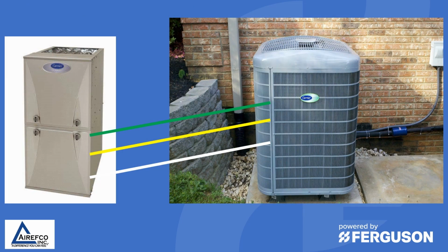The next thing we want to check is the connection to the outdoor unit. There should be 2 or 3 wires going to most of the communicating units that Carrier and Bryant use currently. You will have a green connection, a yellow connection, and sometimes the white wire from the outdoor unit is connected to eliminate a communication problem. So make sure that your green, yellow, and white wires are wired correctly from the outdoor unit to the indoor.